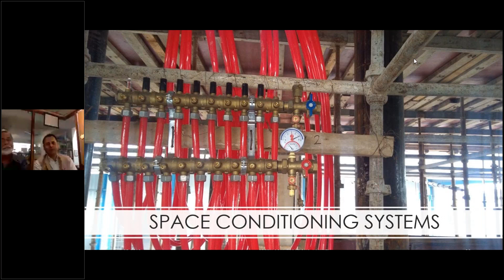So just to tell about the brief of the HVAC system that we have done, the entire building is provided with the standard high side, which consists of our chilled water system. The chiller that we have selected is of 100 ton. So if you have noticed on the first page of the project, the total built-up area was about 50,000 square feet. And with the chilled water and radiant system that we have finalized, the 100 tons gives us approximately 500 square feet a ton. As a comparison, in a conventional building you hardly achieve higher than 250, 220 square feet a ton. So the design of the building was almost double as compared to the conventional building.